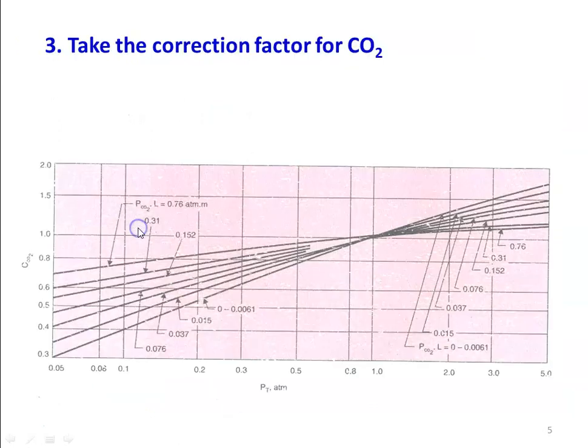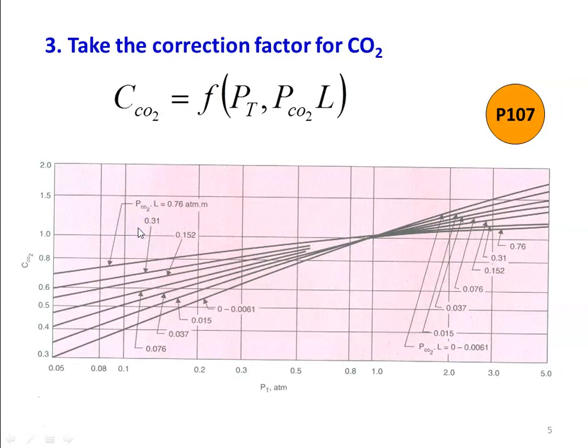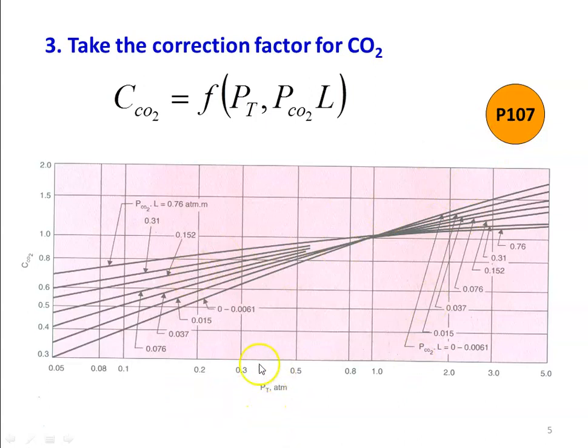We also need to calculate the correction factor for CO₂ (C_CO₂), which is a function of total pressure and the product PCO₂ × L. This graph is on page 107 of the data book. The x-axis is the total pressure of the combustion chamber, and the lines are for different values of PCO₂ × L. Knowing PCO₂ × L and total pressure, we can calculate the correction factor C_CO₂.